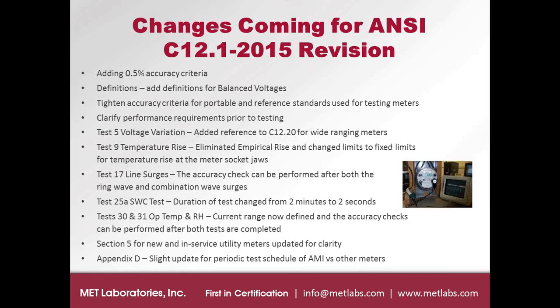Test 30 and 31, that's the operating temperature and the relative humidity. They're similar to test 17. You're now allowed to run the two of those environmental temperature and humidity sequences together and run an accuracy check before and after. You're also looking at the accuracy during these events as well, but it's required that you run an accuracy check before and after. You're allowed to do that now after performing both rather than after each.